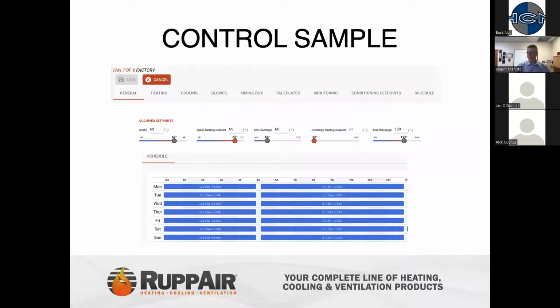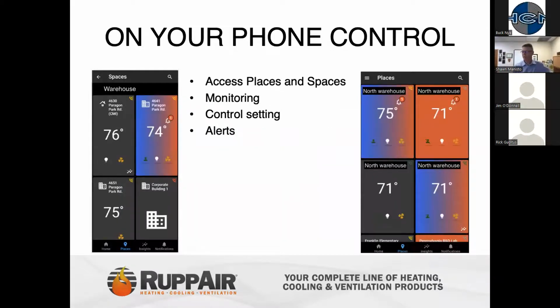And then having easy control. So basically, it's just a snapshot of one of our control screens. All you can basically do, change your intake temperature activation point, change your space set point. You can change your maximum and minimum discharge set points, set a schedule within the system. And on top of that, also having the ability to have this on your phone, having an application in place to be able to do all this within your hand, to access places and spaces within the product, to be able to monitor, control settings, and set yourself alerts on what's going on in the space.